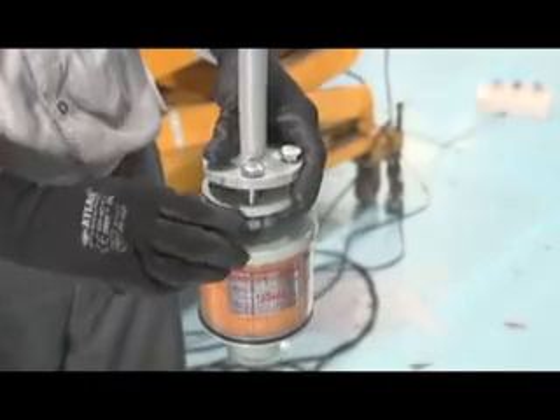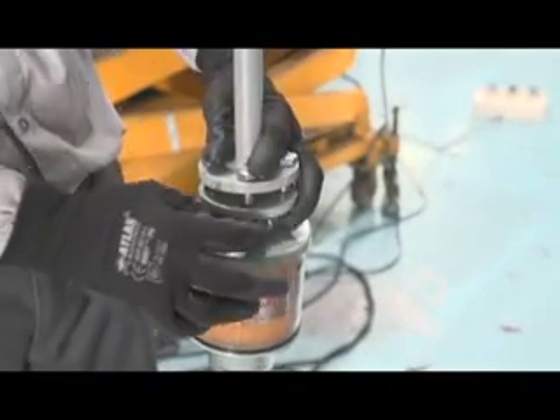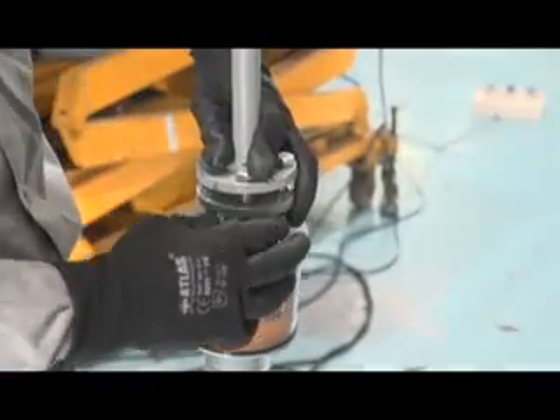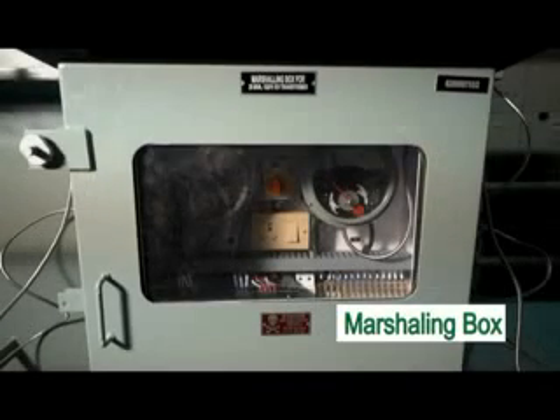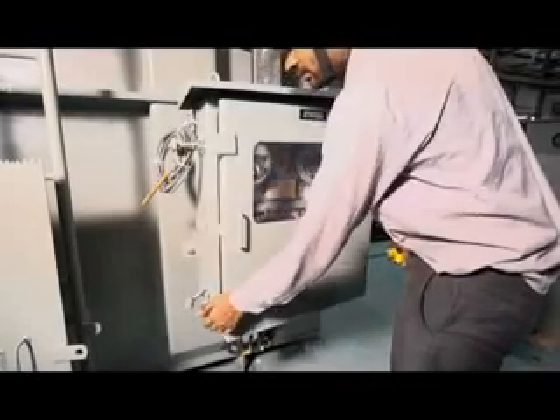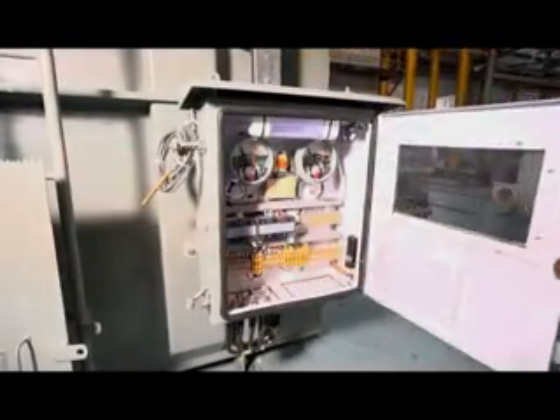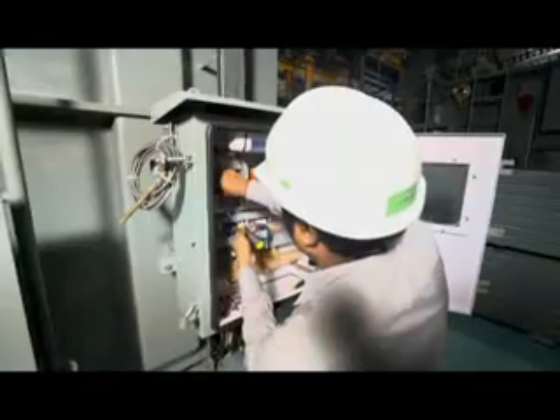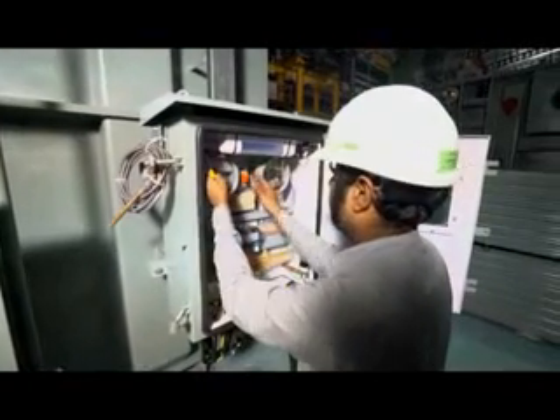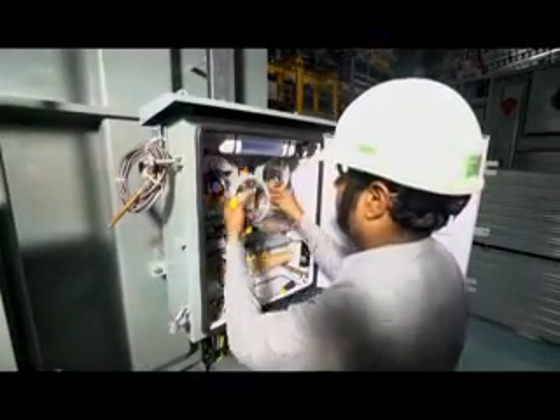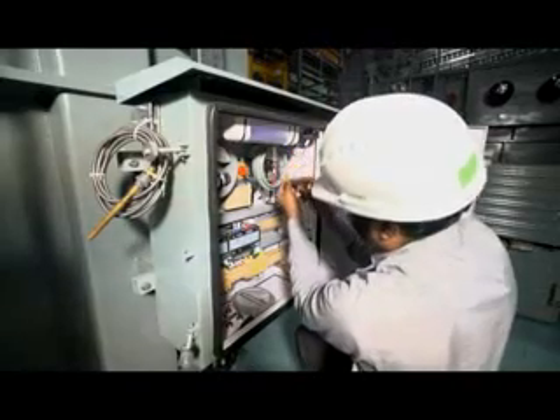Both of these happen when the oil acts as a filter and removes the dust from the outside air. Marshalling box. As the name implies, this is the master control panel for the protection devices. This is a panel with a door, part of which is glass, allowing easy visibility of the instruments and their readings. This houses indicating instruments.